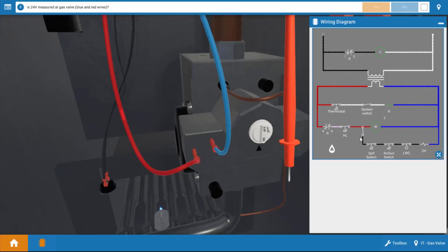The first one being the vent damper end switch, which is a proving switch for the vent damper, a spill switch, rollout switch, and a low water cutoff. So it's possible our gas valve is faulty, but it's also possible that any one of these safety switches is open as well.